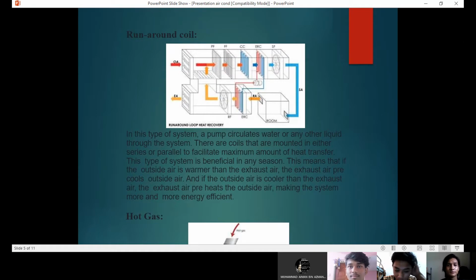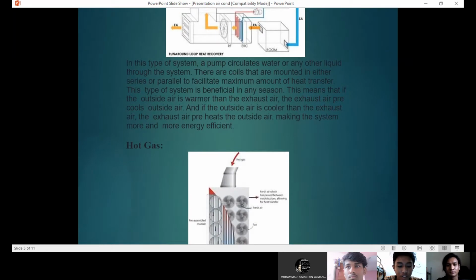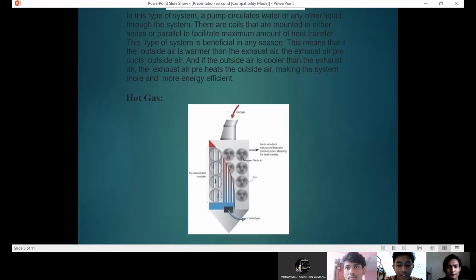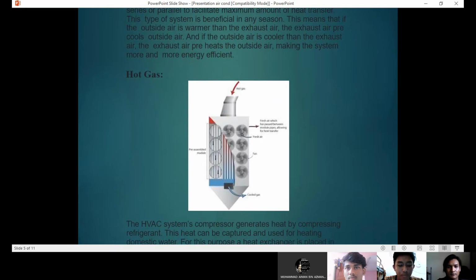Seterusnya saya akan sambung run around coil. In this system, a pump circulates water or any other liquid through the system. There are coils that are mounted in either series or parallel to facilitate the maximum amount of heat transfer. This type of system is beneficial in any season. This means that if the outside air is warmer than the exhaust air, it pre-cools the outside air. And if the outside air is cooler than the exhaust air, it preheats the outside air, making the system more energy efficient.